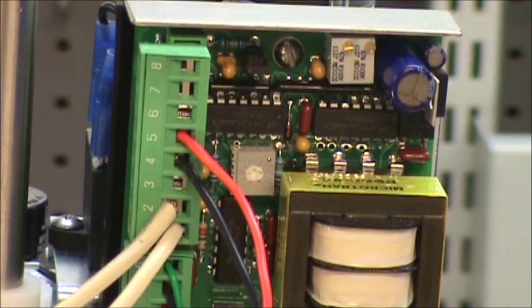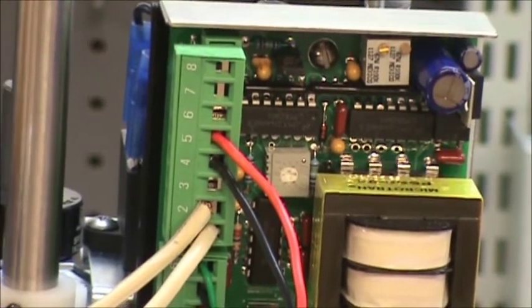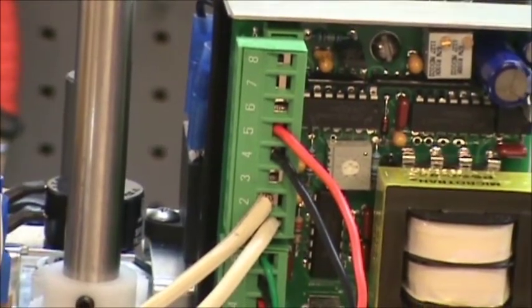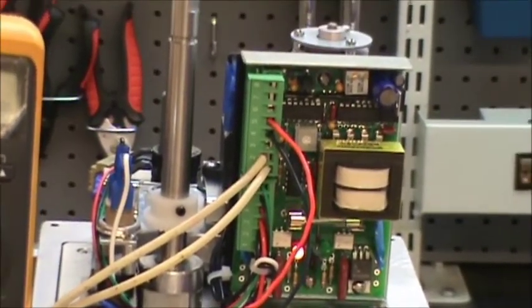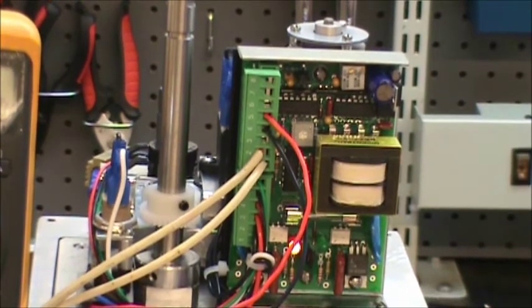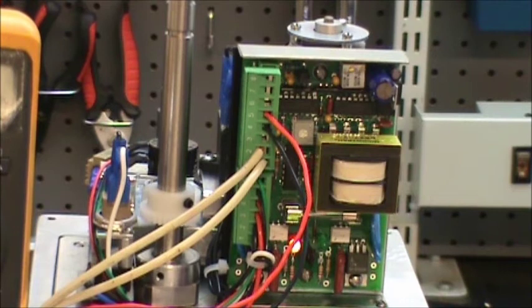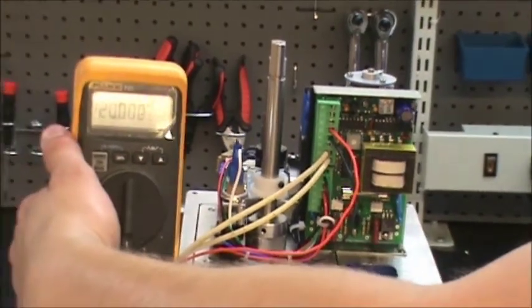The span controls the open, so you're going to give it a 20 milliamp signal. And you'll notice the red LED light down here is on. That light will stay on as long as it's traveling. If the actuator stops operating and that light is still lit, that means once again you've reached the factory set travel limits. Then you're going to want to turn it counterclockwise.